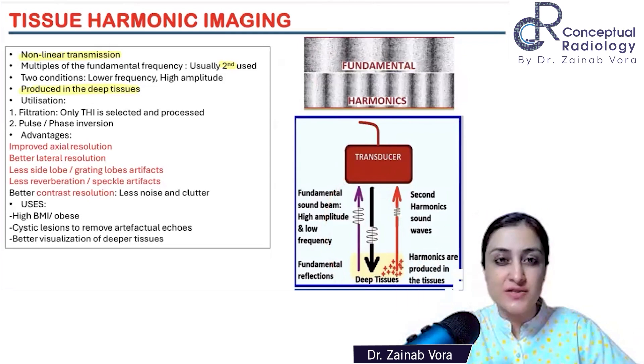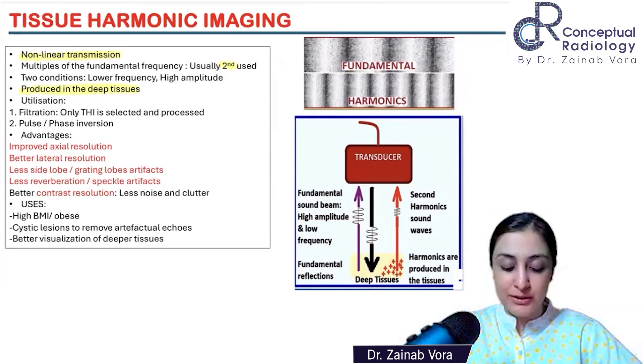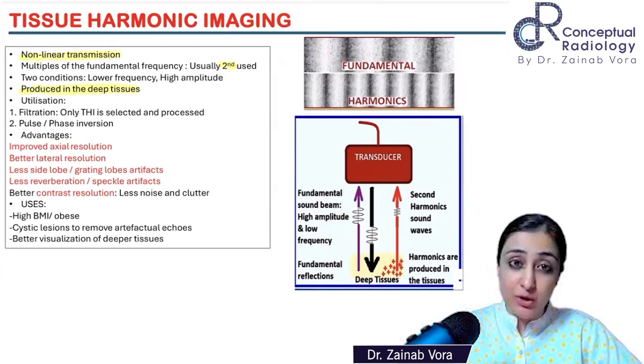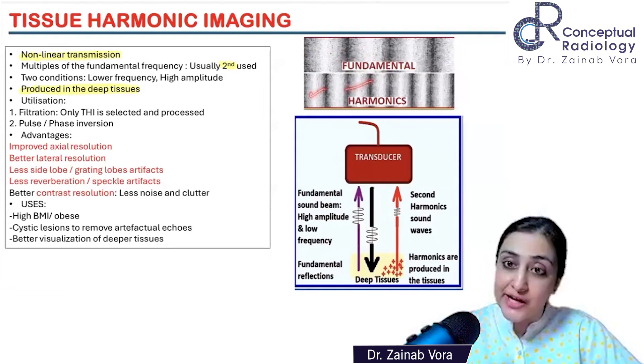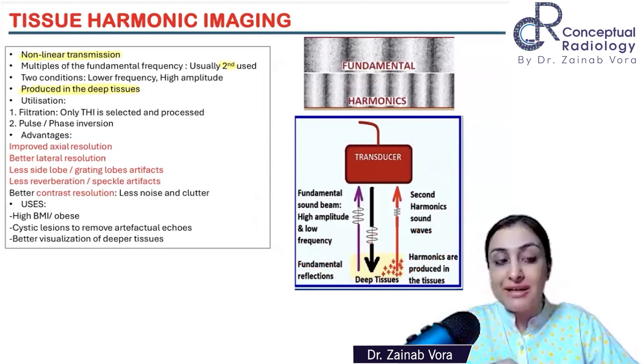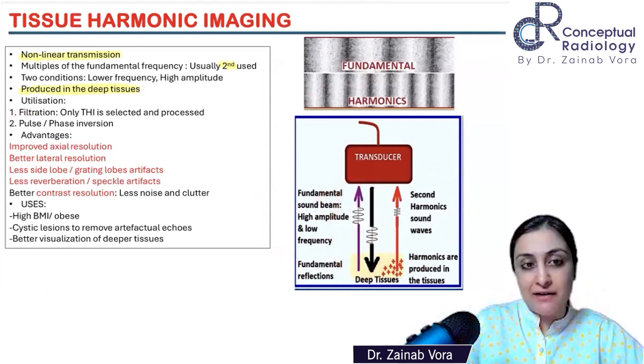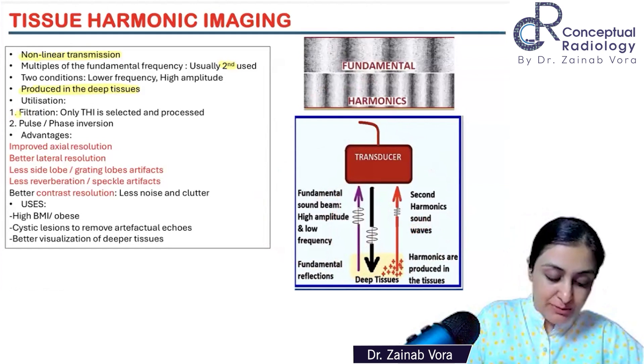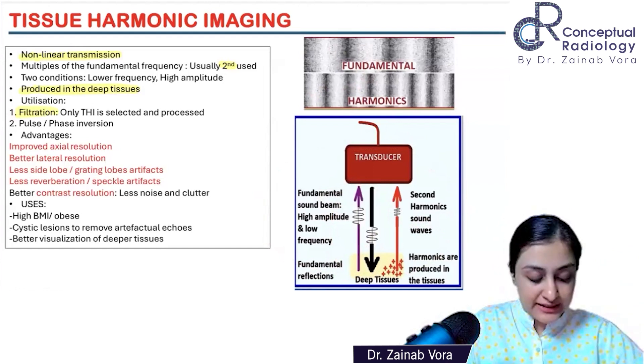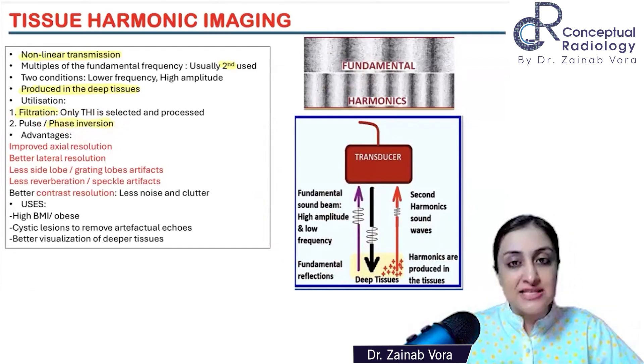Harmonics are the second to third frequency — that is what we are using. The fundamental wave is compression-rarefaction; harmonics are at a higher frequency. So how does the machine decide whether to take the fundamental or second harmonic? There are two ways. One is filtration — you filter out the fundamental beam and have the machine only take the harmonic. But that did not give very good images. So more commonly we now use another technique called phase inversion. You would have heard of phase inversion if you have ever read about CEUS.